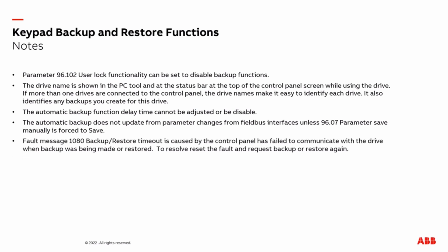Fault message 1080, backup restore timeout, is caused by the control panel failing to communicate with the drive when a backup was being made or restored. To resolve, reset the fault and request a backup or restore again. You will not lose information or damage the drive.